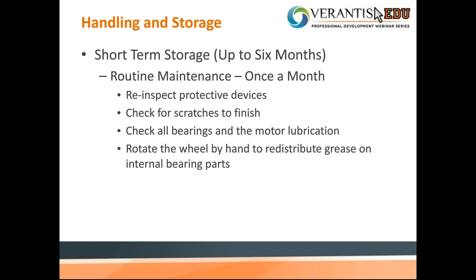So, like I said, there are two different types of storage: short-term and long-term storage. With short-term storage, routine maintenance is key, and you've got to do it at least once a month. So, re-inspect the protective devices. Check for scratches to the finish to make sure nothing has run into it or taken an abrupt hit. Check all bearings and motor lubrication. Rotate the wheel by hand and redistribute the grease on the internal bearing parts. Typically in the manual there will be instructions on short-term and long-term storage.